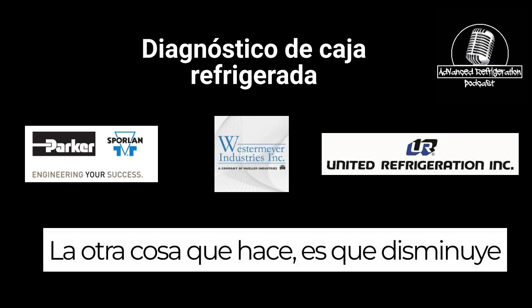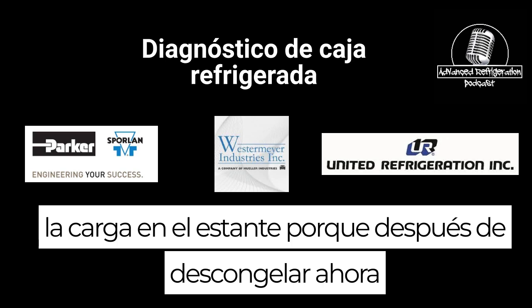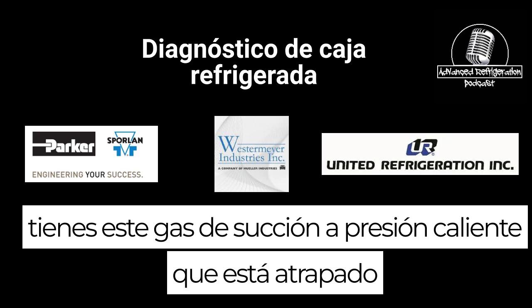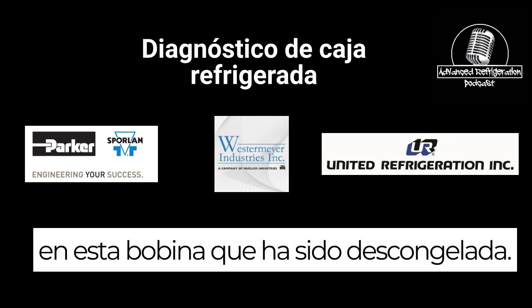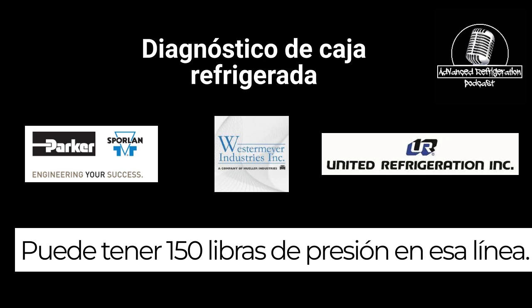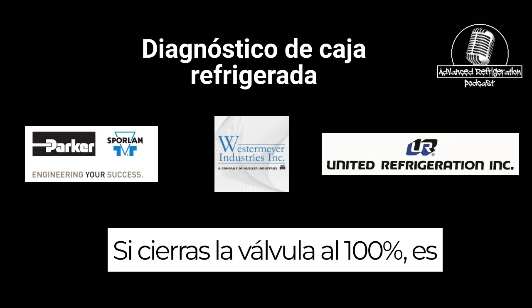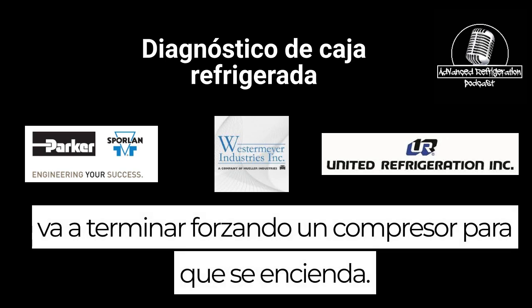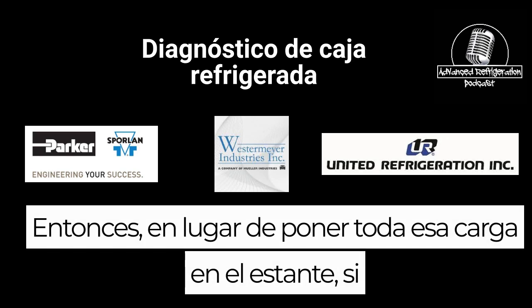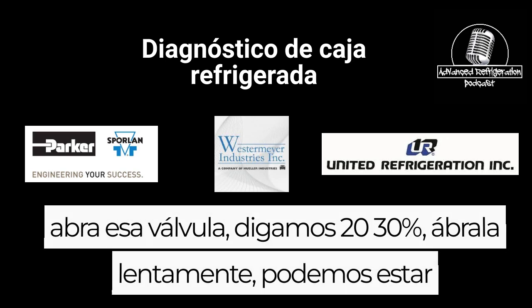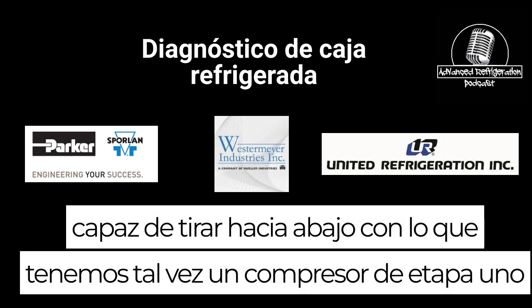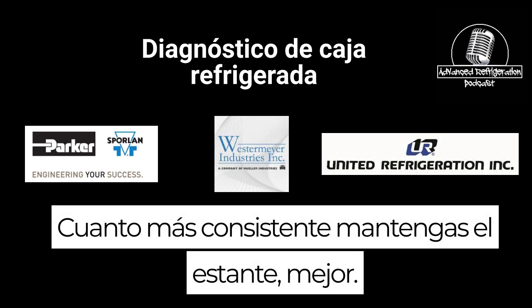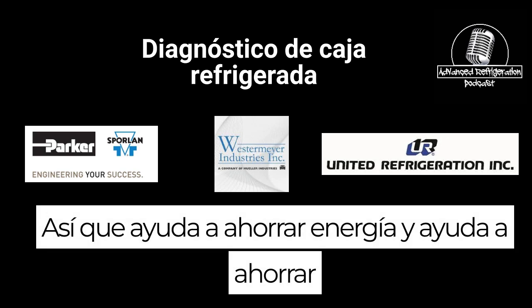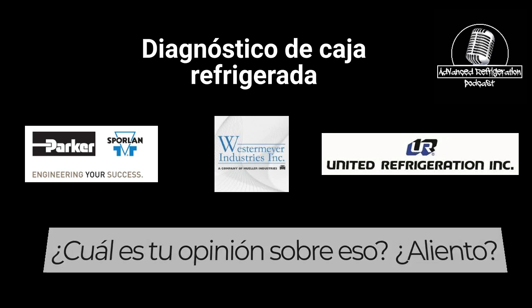The other thing it does, it lessens the load on the rack, because post defrost you've got this hot pressure suction gas that's trapped in this coil that's been defrosted. You may have 150 pounds of pressure in that line. If you slam that valve open to 100%, it's going to end up forcing a compressor or two on. It's going to increase your suction pressure. So instead of putting all that load on the rack, if we open that valve, say 20, 30%, open it slowly, we may be able to pull down with what we have, maybe stage one compressor on or an unloader on. That way we're not just slamming the rack on and off at every defrost. And the more consistent you keep the rack, the better. So it helps save energy and helps save wear and tear on the rack. What's your thoughts on that, Brett?